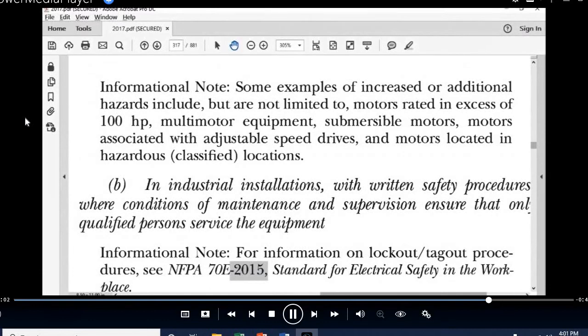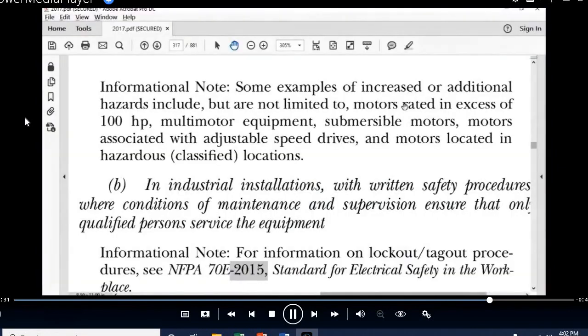of increased or additional hazards include, but are not limited to, motors rated in excess of 100 horsepower. I don't understand it. I don't know, Eric. I guess if you have a very large motor, you don't want to have a disconnect next to the motor, and you don't want to open the disconnect next to the motor. Is that true? That's correct. There are some compressors that cost millions of dollars, and if you have a disconnect next to the motor, there are very rigid start and stop sequences to the motor. Having a disconnect next to the motor can destroy $1 million very quickly. Submersible motors, we talked about that. Motors associated with adjustable speed drives.